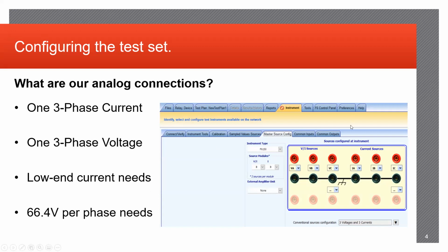So this is a quick little screenshot of what you'd see when you're initially opening up the software. In this instrument tab, you can identify your sources as discussed earlier. You can actually change these from your voltage to currents and flip-flop, et cetera. You can also utilize the underside ports as well for additional voltage or current sources, especially when you're doing end-to-end testing that may include different directional current elements that may be utilized for pickup purposes.